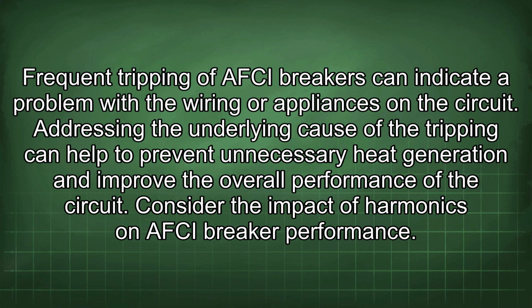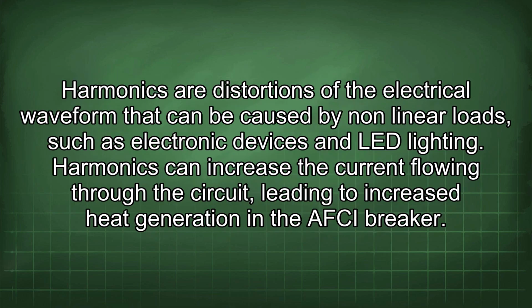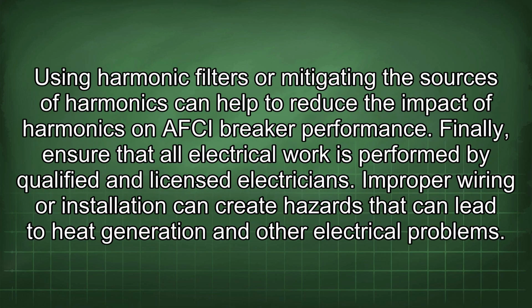Consider the impact of harmonics on AFCI breaker performance. Harmonics are distortions of the electrical waveform that can be caused by nonlinear loads such as electronic devices and LED lighting. Harmonics can increase the current flowing through the circuit, leading to increased heat generation in the AFCI breaker. Using harmonic filters or mitigating the sources of harmonics can help to reduce the impact of harmonics on AFCI breaker performance.